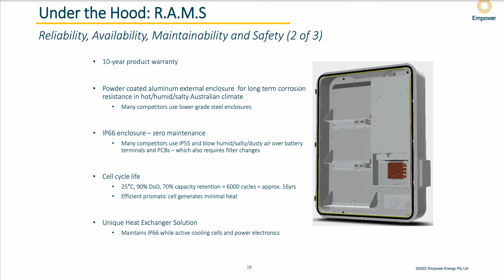What about the cell life - is there any fade in capacity over time? Cycle life depends a lot on temperature. These cells have a pretty long lifetime rating: at 25 degrees C, 90% depth of discharge, which is all we allow them to go through, they can go 6,000 cycles and maintain 70% of their capacity over that time. That's about 16 years, assuming one cycle per day. Though it's a 10-year warranty or 45 megawatt hours, whichever comes first.